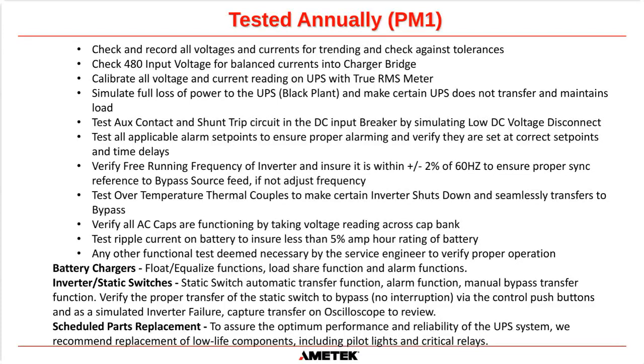We also simulate a full loss of power to the UPS to make sure that the UPS does not transfer and maintains load. In other words, if you lost all modes of power, all AC from your switch rooms to this UPS, then the system is going to go onto battery, and we want to make sure that the system will handle that without any issues.